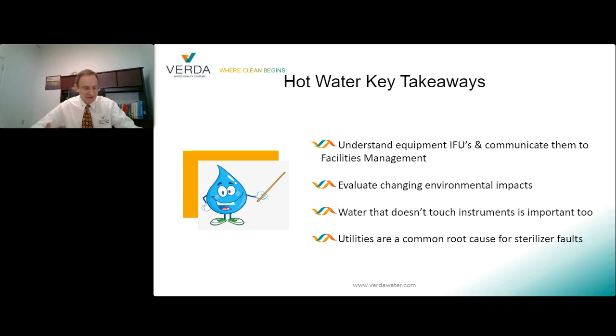When the equipment was installed, no one looked at the possibility of the water temperature seasonally fluctuating and that impacting equipment performance. Quick question: how much does the water temperature at your hospital change over the course of the year? Are you even checking this? The facility and the SPS were laser focused on AAMI TIR34 for washing and for rinsing and for sterilization of instruments. They didn't look closely at the non-AAMI compliant water requirements that the OEM, the equipment manufacturer, had for it, because that water wasn't touching the instruments.